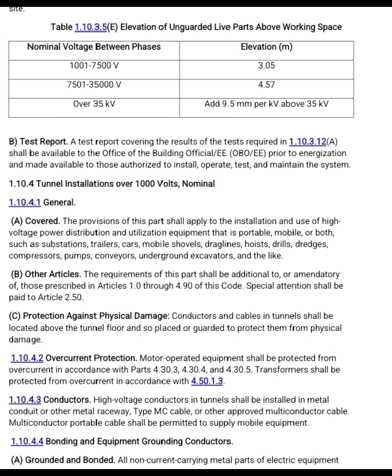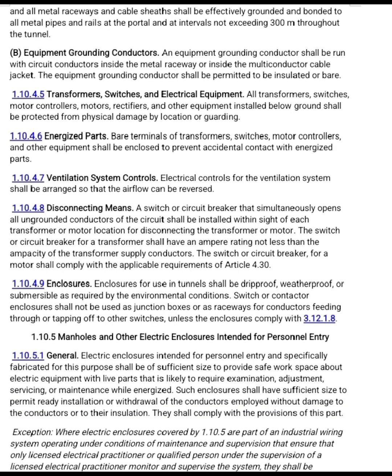1.10.4 This section explains rules for installing high voltage equipment in tunnels. 1.10.4.2 Equipment must have protection to stop too much current from flowing, which prevents overheating or fire. And all metal raceways and cable sheaths shall be effectively grounded and bonded to all metal pipes and rails at the portal and at all intervals not exceeding 300 m throughout the tunnel.